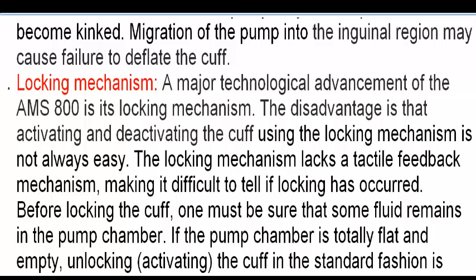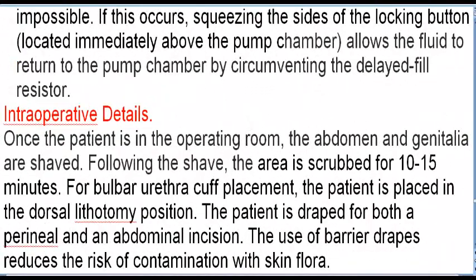Locking mechanism. A major technological advancement of the AMS 800 is its locking mechanism. The disadvantage is that activating and deactivating the cuff using the locking mechanism is not always easy. The locking mechanism lacks a tactile feedback mechanism, making it difficult to tell if locking has occurred. Before locking the cuff, one must be sure that some fluid remains in the pump chamber. If the pump chamber is totally flat and empty, unlocking and activating the cuff in the standard fashion is impossible. If this occurs, squeezing the sides of the locking button, located immediately above the pump chamber, allows the fluid to return to the pump chamber by circumventing the delayed fill resistor.